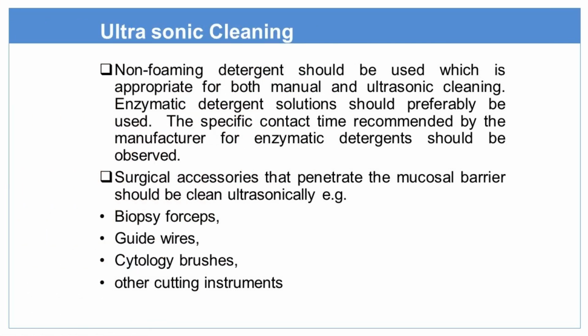Ultrasonic cleaning. The other accessories we use in endoscopy require ultrasonic cleaning. It's mandatory also. A non-foaming detergent should be used during ultrasonic cleaning. Surgical accessories that penetrate the mucosal barrier should be cleaned ultrasonically, like biopsy forceps, guide wires, cytology brushes, and other cutting instruments. All these things need ultrasonic cleaning.